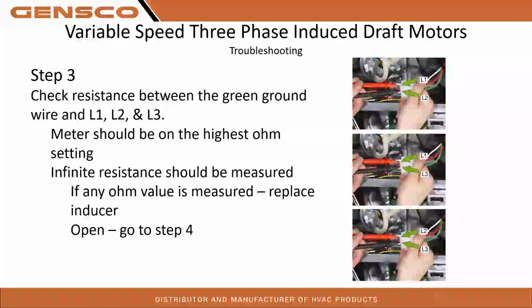All right, so troubleshooting. We're going to check resistance. Meter should be set on the highest ohm rating. Infinite resistance should be measured. If any ohm value is measured, replace the inducer. Okay, so we're checking the ohm values between 1, 2, and 3, on the highest ohm setting on your meter. They should all be equal and even.